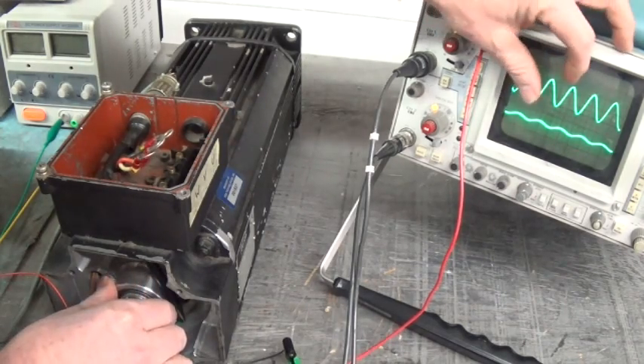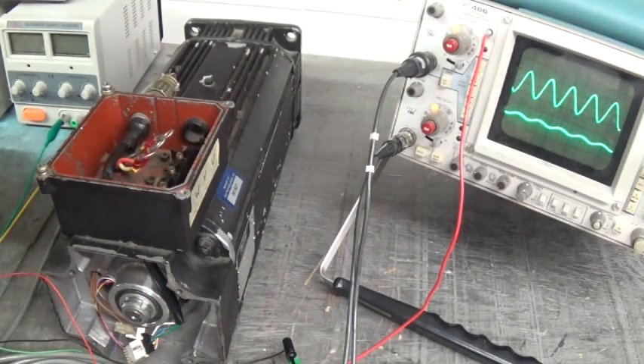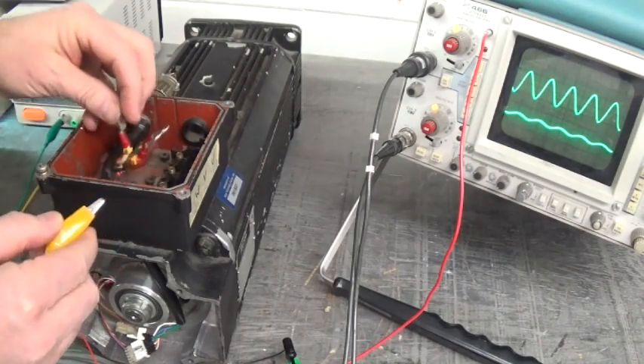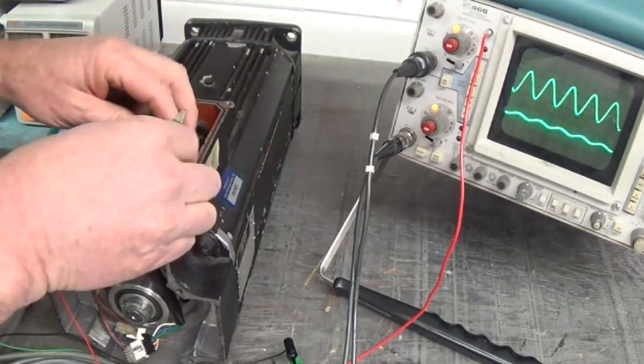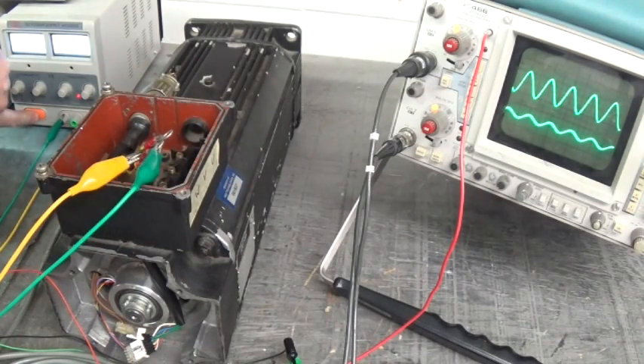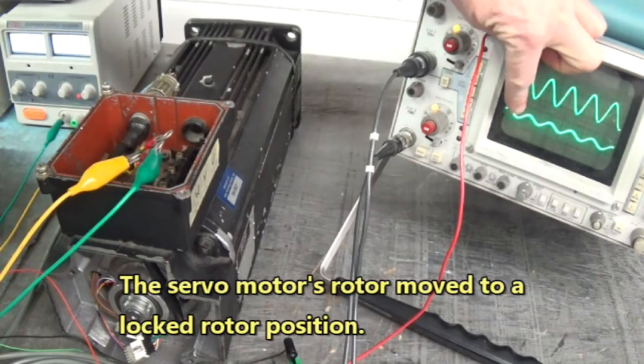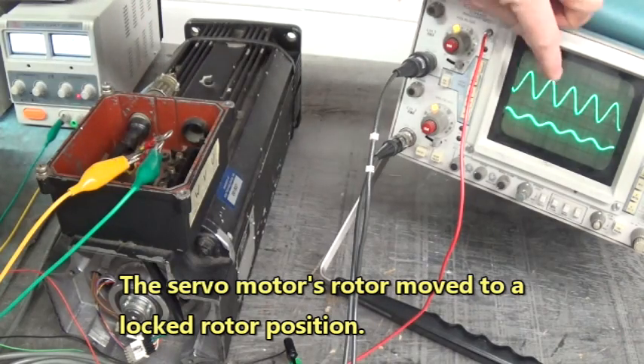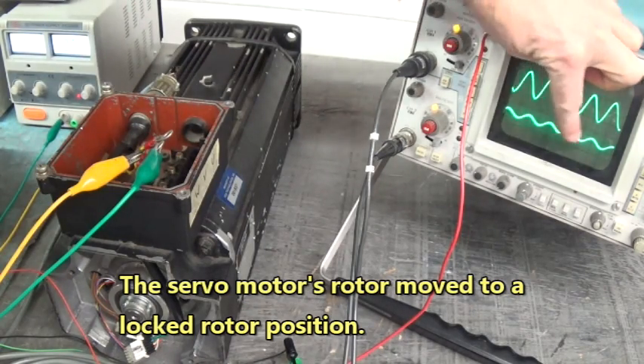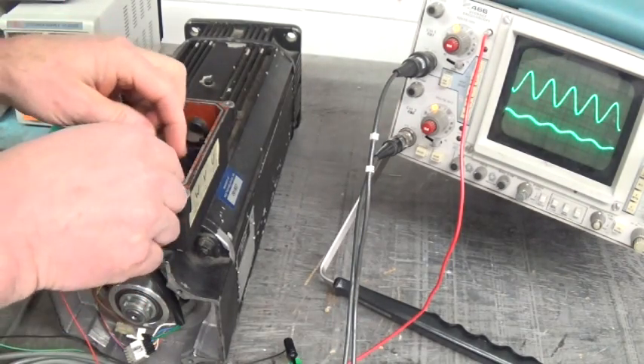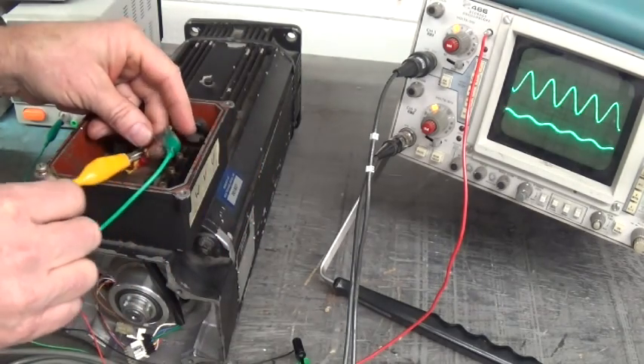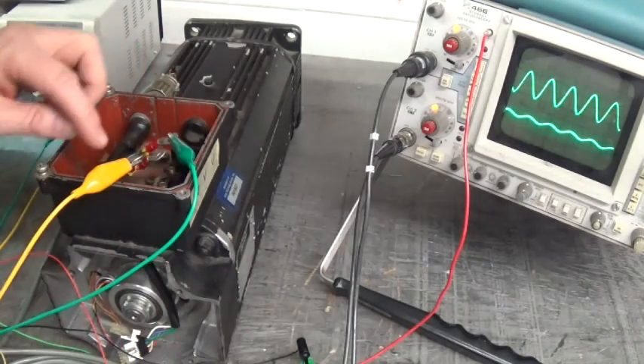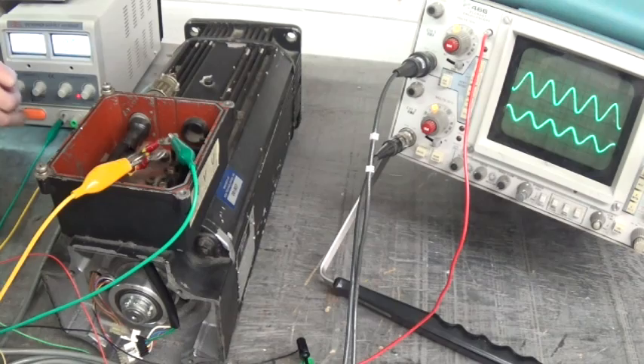Let me show you how it works. We'll start here. This is W. We'll put positive on W, we'll put ground on V, turn it on. Okay, that condition is not satisfied. We can see right here that we have a sine and a cosine, so let's turn the power supply off, move our ground to U, we'll leave the positive on W. Okay, the condition is not satisfied.